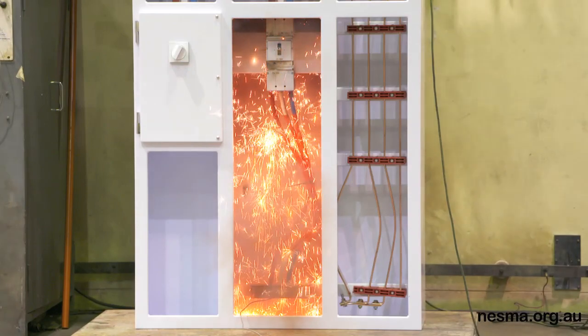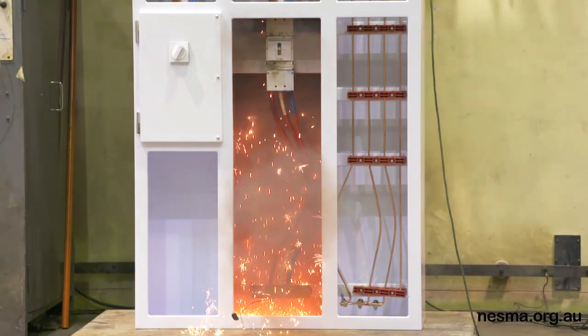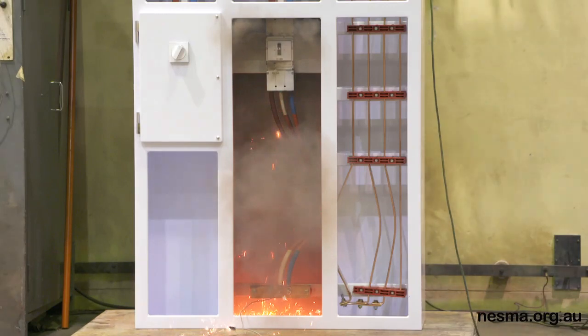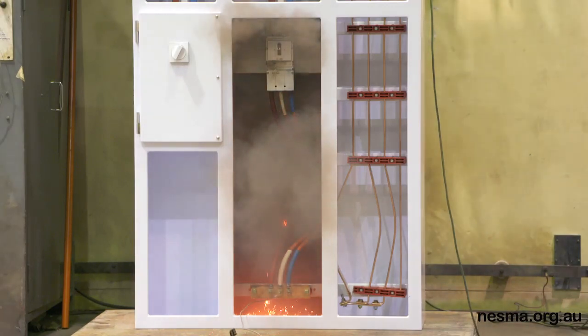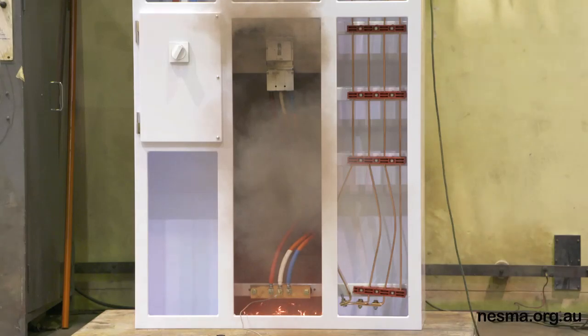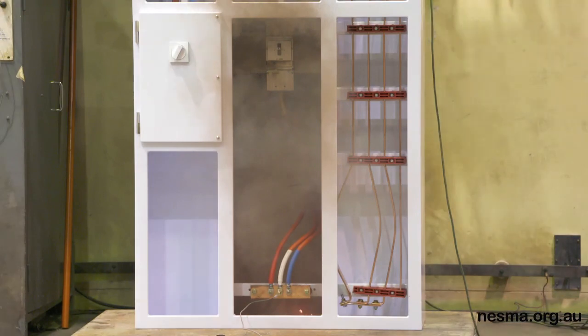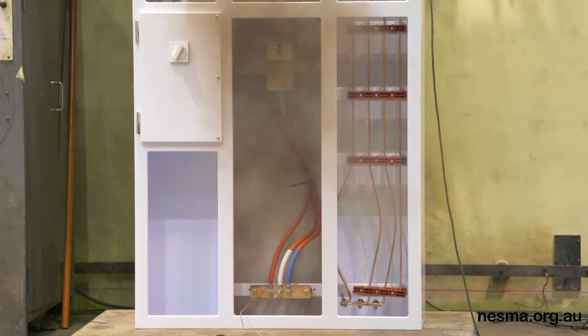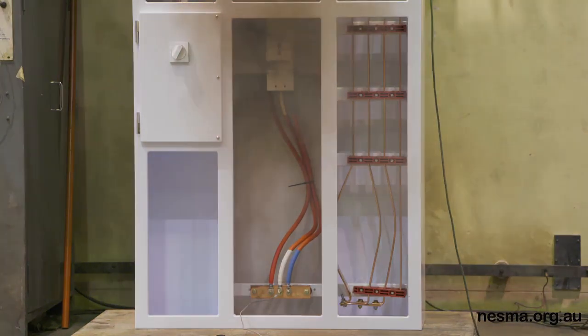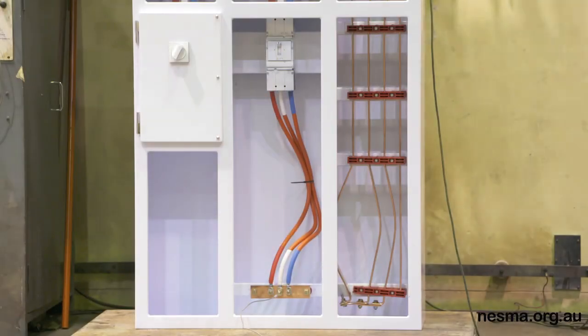Now what we're seeing is the circuit breaker detecting the fault. I haven't seen the oscillogram, but I would expect that the operate time of the circuit breaker was sub 10 milliseconds. So as the current came on, it has a high rate of rise in the current. The breaker detects that, and then it just turns the supply current off. We had the 50 kA line side test, conditional rating on the line side.